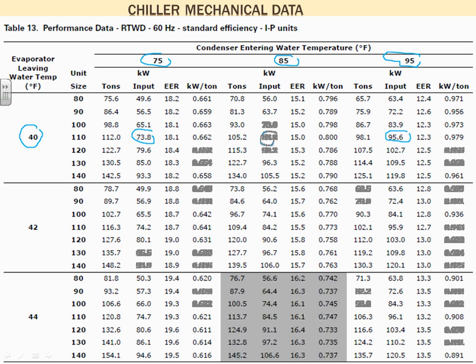And then here's the value that you use. Can you guys see that one? This is a kilowatt per ton. What's your value when they say a 500 ton chiller? How many kilowatts is the 500 ton chiller? 500. Well, in this case, one to one. Certain manufacturers, if you go down on these, it goes lower than one even, the ratio between kilowatt to ton. So that's based on the equipment. So it gives you the kilowatt to ton ratio.